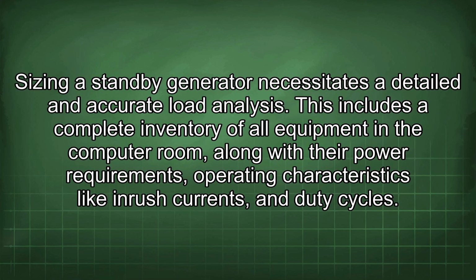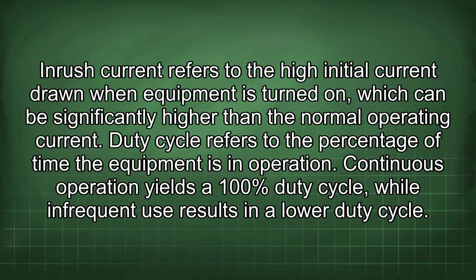Sizing a standby generator necessitates a detailed and accurate load analysis. This includes a complete inventory of all equipment in the computer room, along with their power requirements, operating characteristics like inrush currents, and duty cycles. Inrush current refers to the high initial current drawn when equipment is turned on, which can be significantly higher than the normal operating current. Duty cycle refers to the percentage of time the equipment is in operation. Continuous operation yields a 100% duty cycle, while infrequent use results in a low duty cycle.